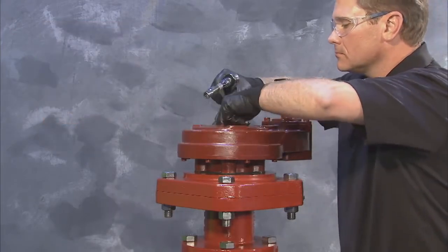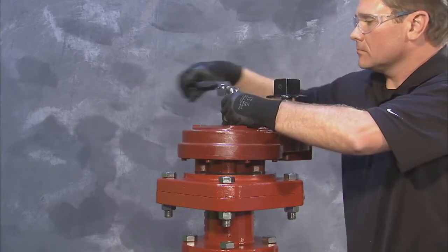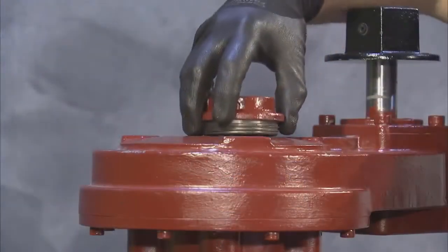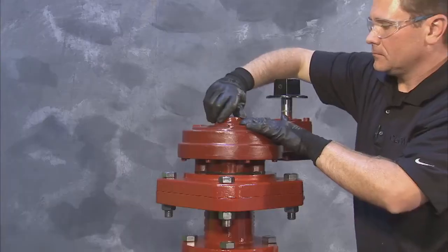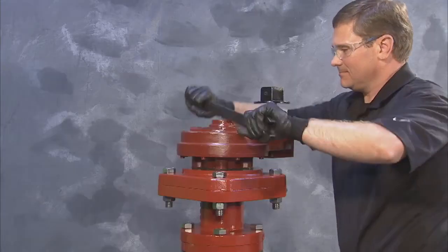Attach and tighten the washer and stem screw and rotate the gearing op nut in either direction to confirm that the gear is moving the valve stem. Finally, reinstall the pipe plug cap and tighten to complete your large valve gear spur or bevel gear changeout.